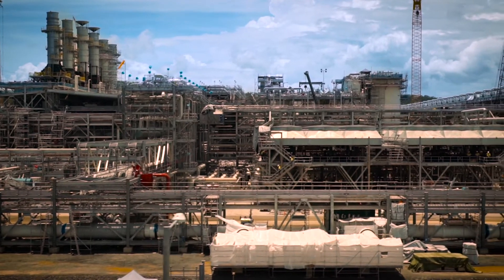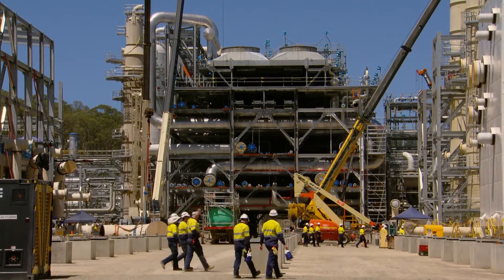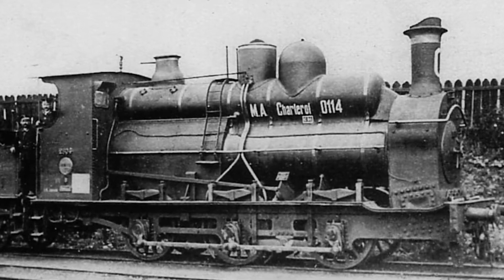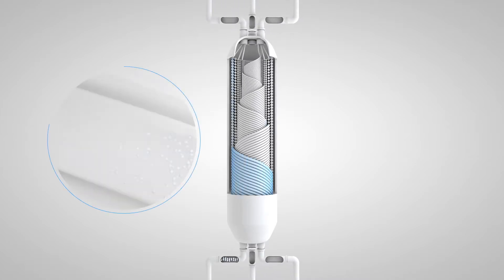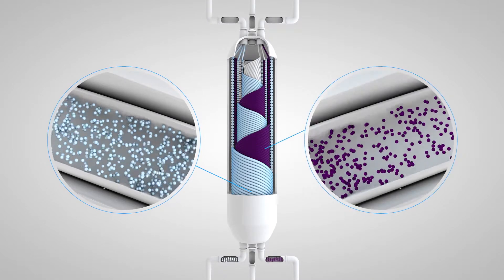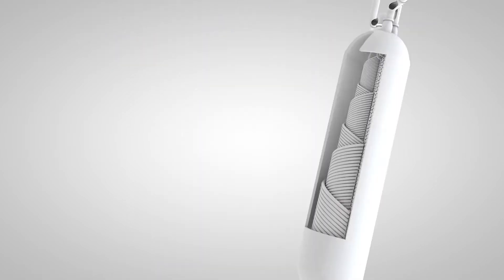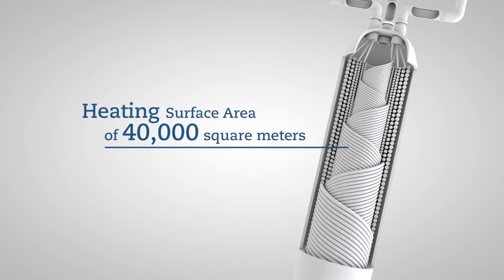But the heart of an LNG plant is the exchanger that cools the natural gas. The two types are coil wound and plate fin. Coil wound heat exchangers have been around the longest, evolving from 19th century locomotive boilers. Today we wind multiple layers of tubes inside a pressure vessel shell. Natural gas and high pressure refrigerant both cool as they flow up inside the tubes. Very cold refrigerant flows down around the tubes in the shell.